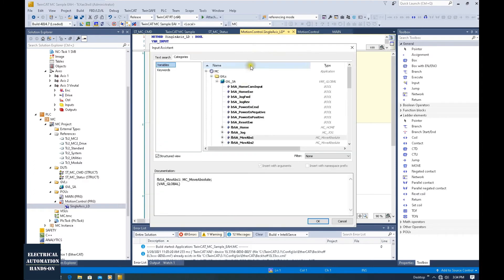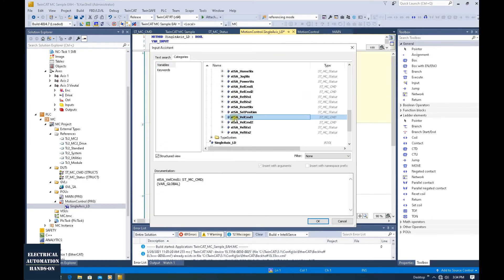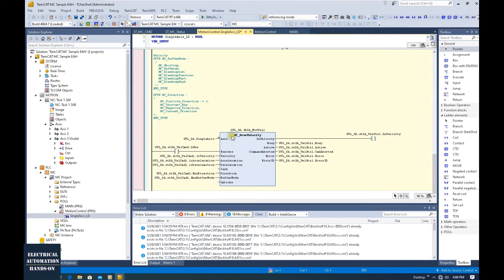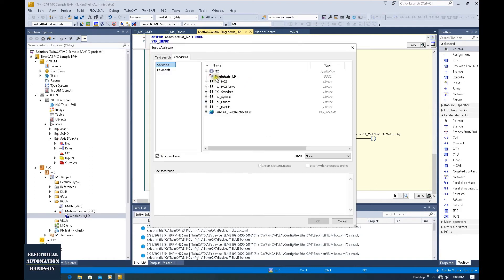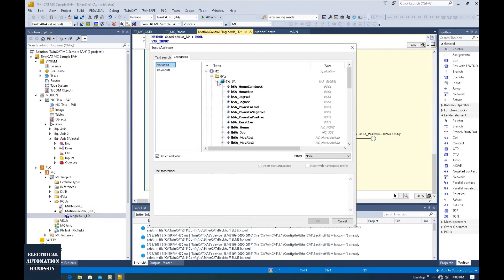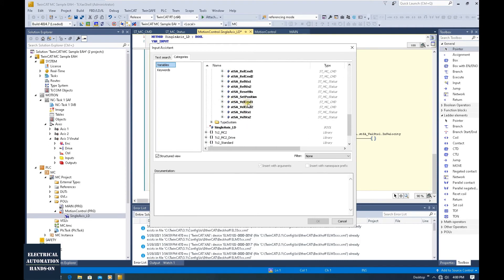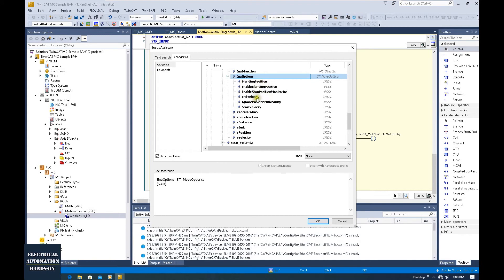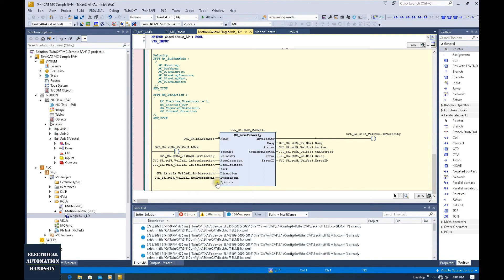Click the small button to find ST_SA_VelocityCommand1. Within velocity command 1, assign execute, and similarly for other input interfaces. For MC velocity, insert all variables: execute, velocity, acceleration, deceleration, direction, and buffer mode. For options, you can leave it as open — without putting a value here — as normally we leave it as default. This covers the typical function block tags: left side is commands, right side is status.